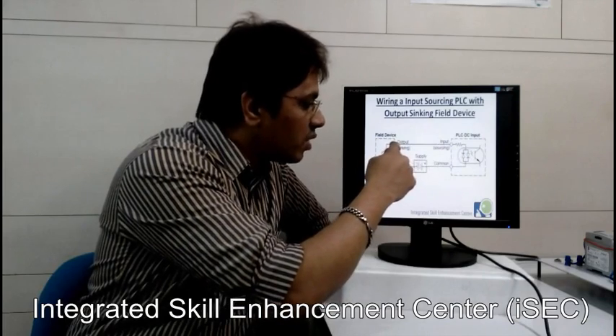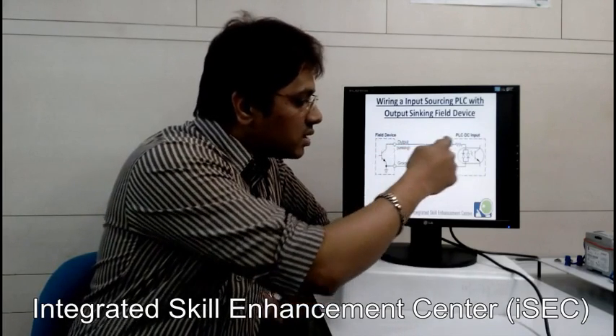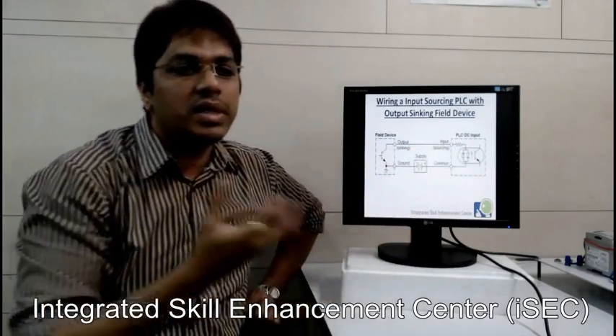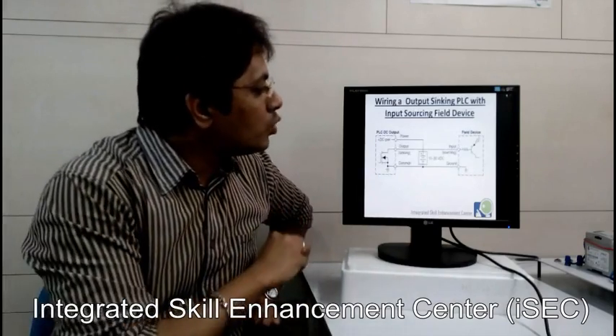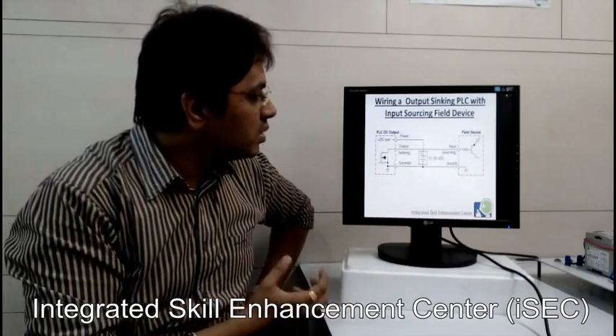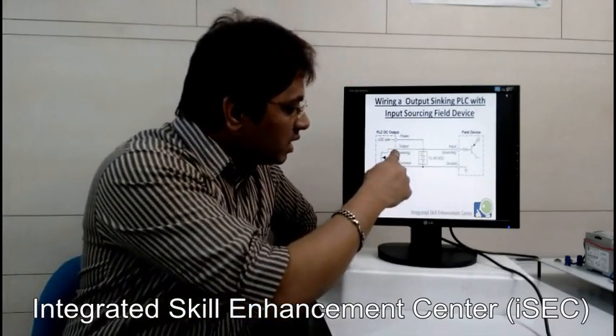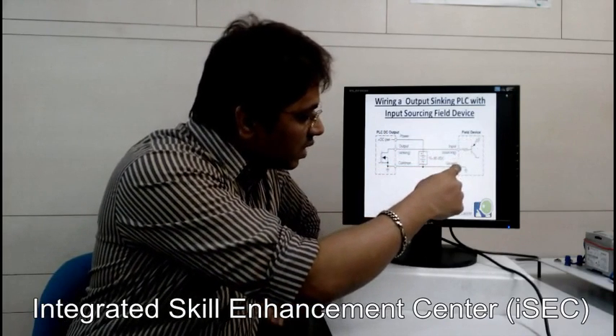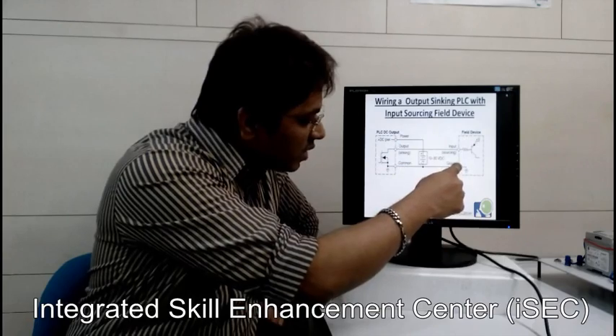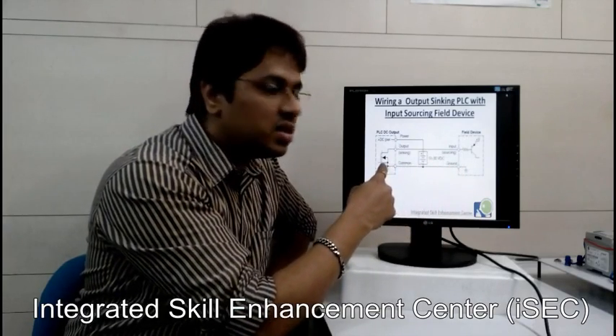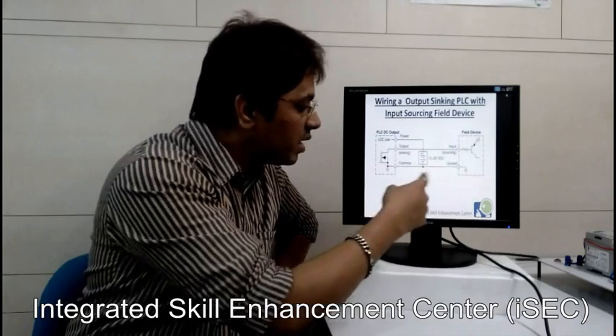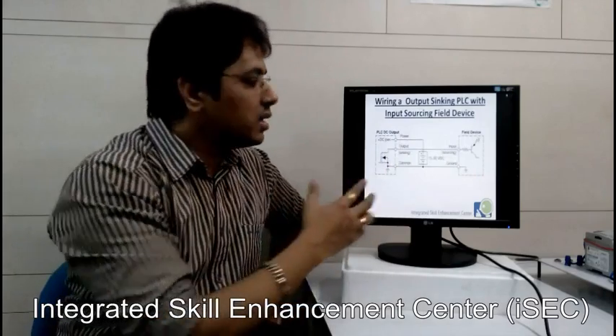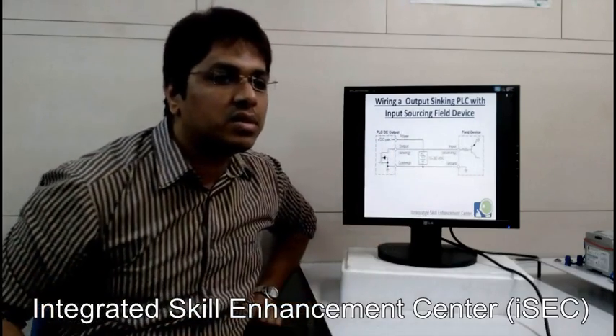The signal from the field device output will act as ground, so the common point at VCC completes the path and the PLC takes the input. For wiring a sinking output PLC with a sourcing input field device: the PLC output gives a ground, causing conduction. The field device ground is connected to the PLC common, so common ground is there, the output sinks, and the path completes — you get the output from the PLC.